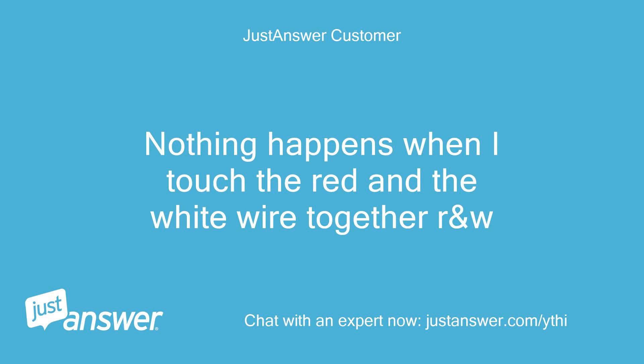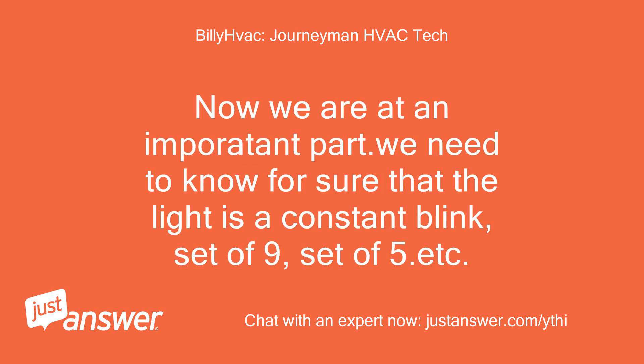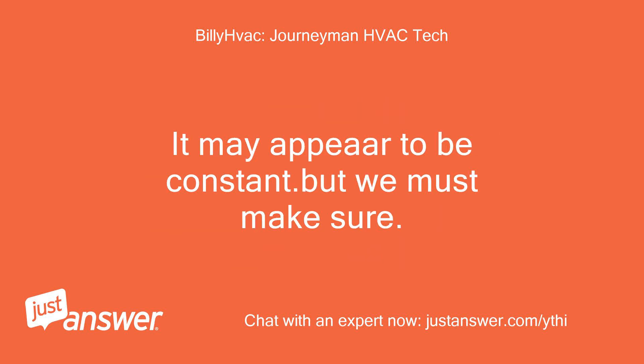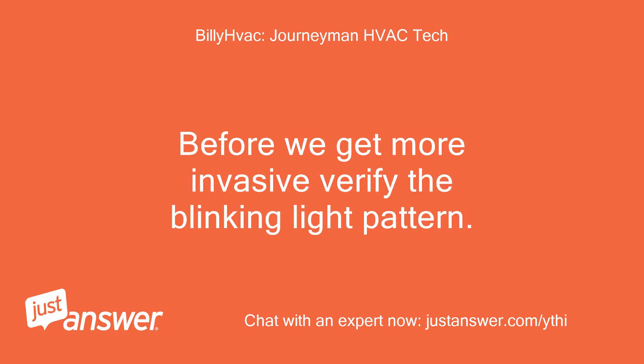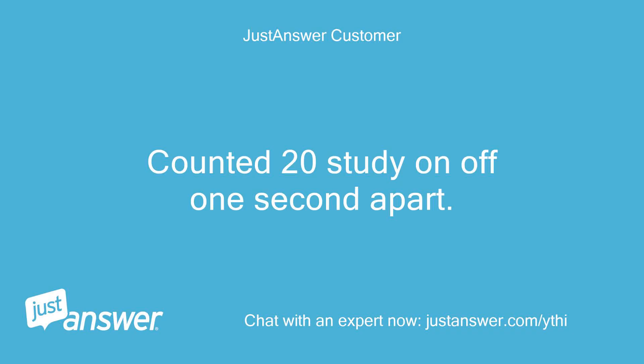Nothing happens when I touch the red and the white wire together — R and W. Now we are at an important part: we need to know for sure whether the light is a constant blink, a set of 9, a set of 5, etc. It may appear constant, but we must make sure. Before we get more invasive, verify the blinking light pattern. Is the filter clean? Is the blower running? Count it — study 20 on/off cycles, one second apart.